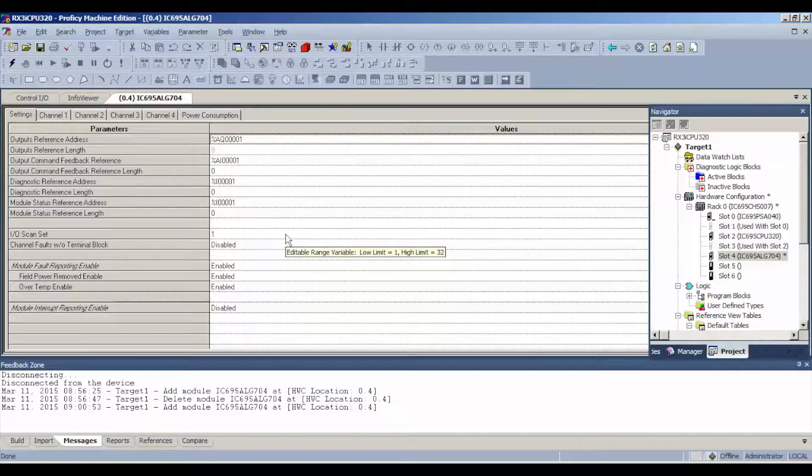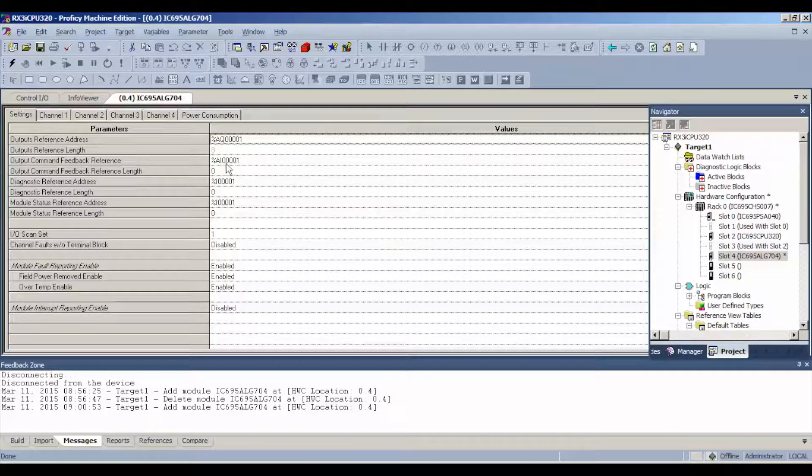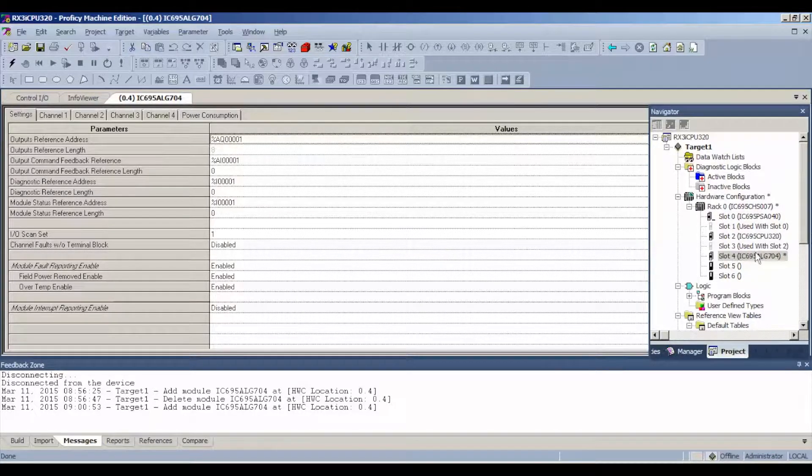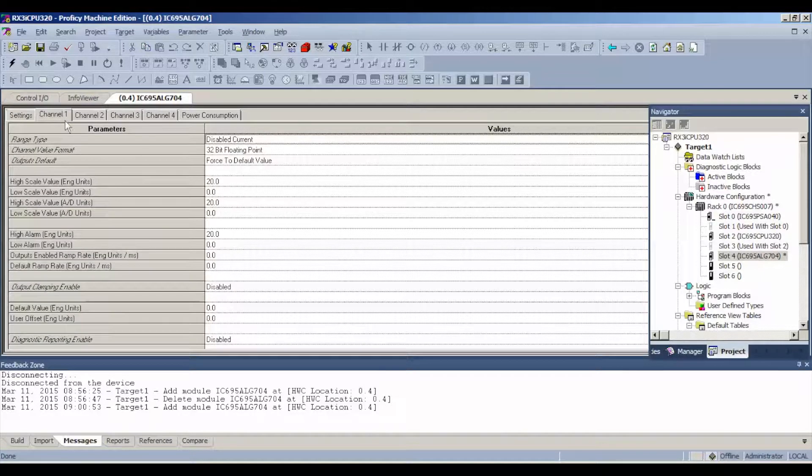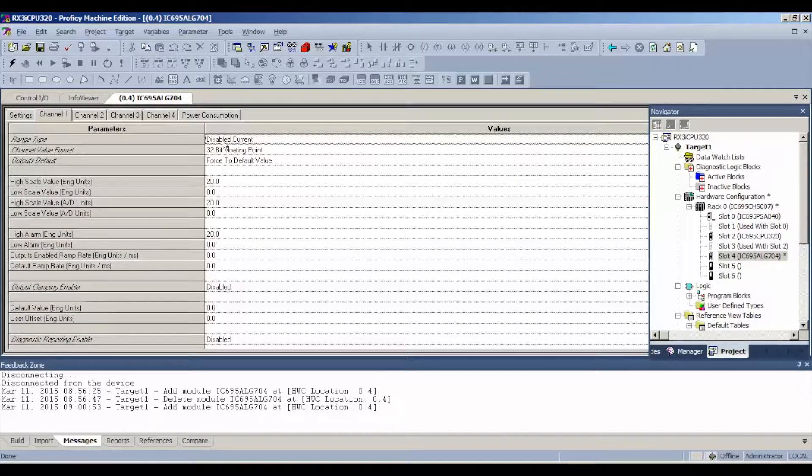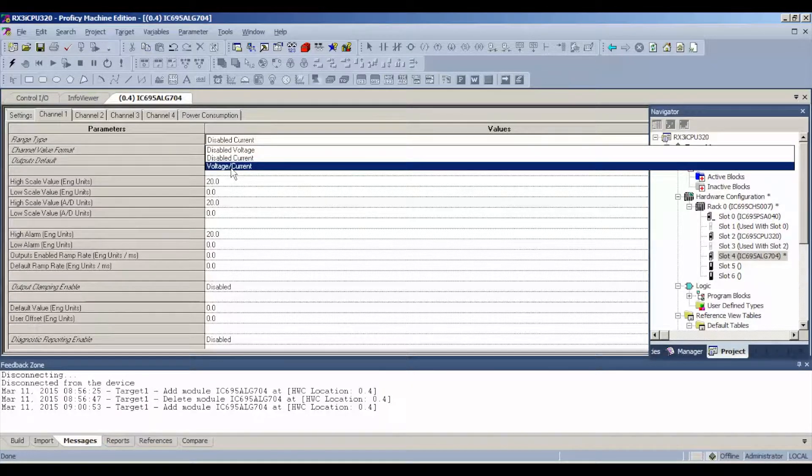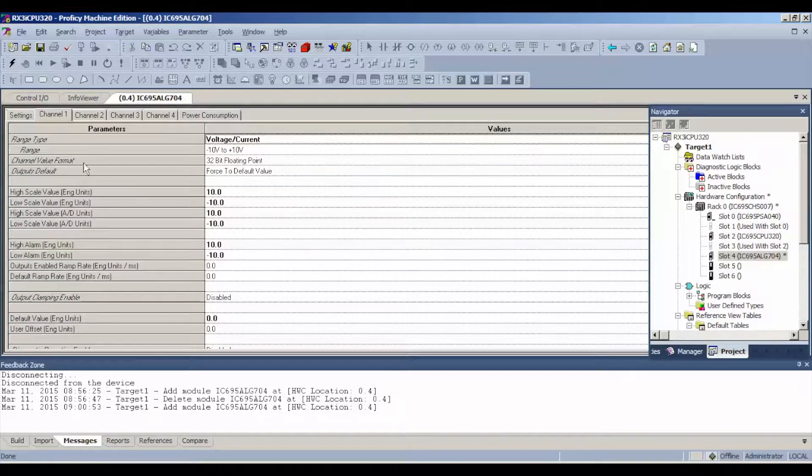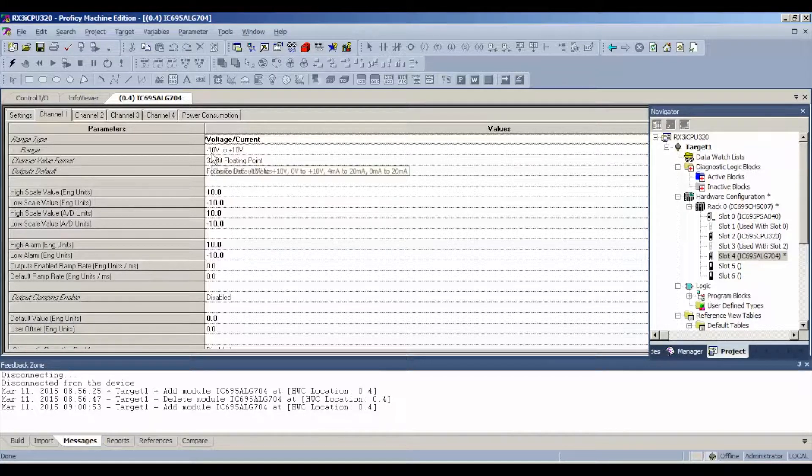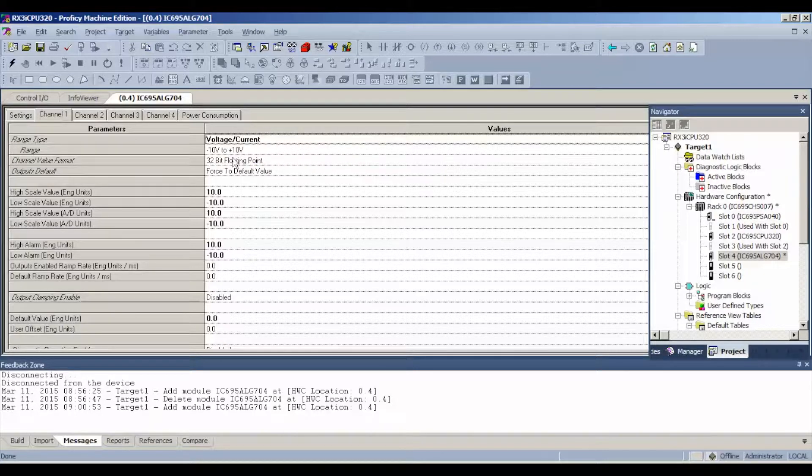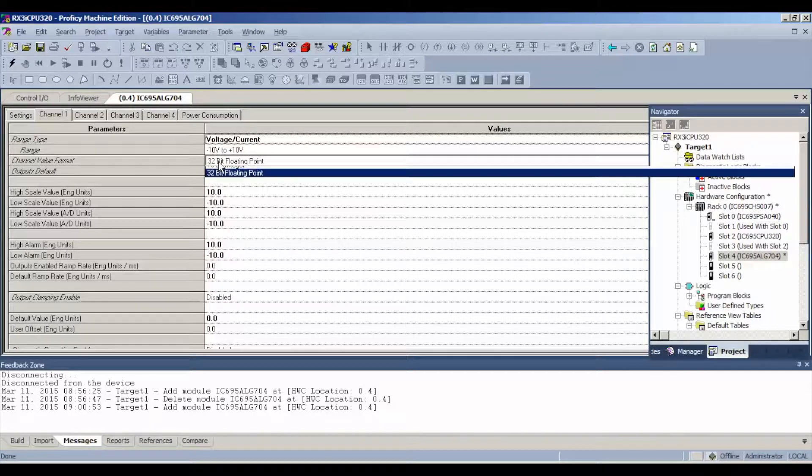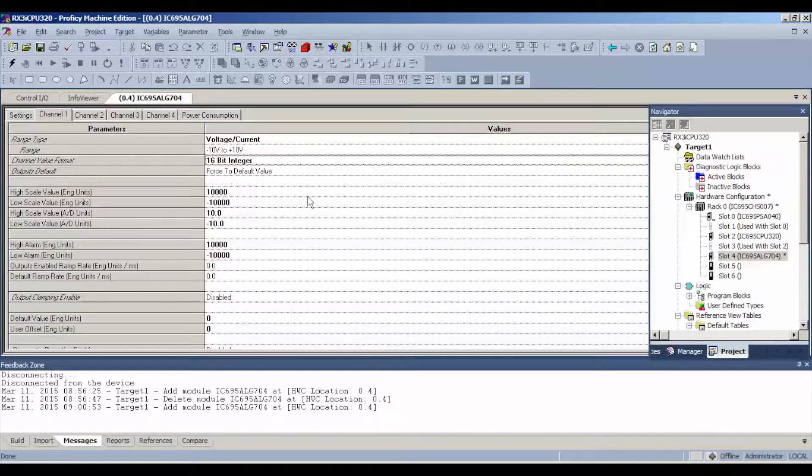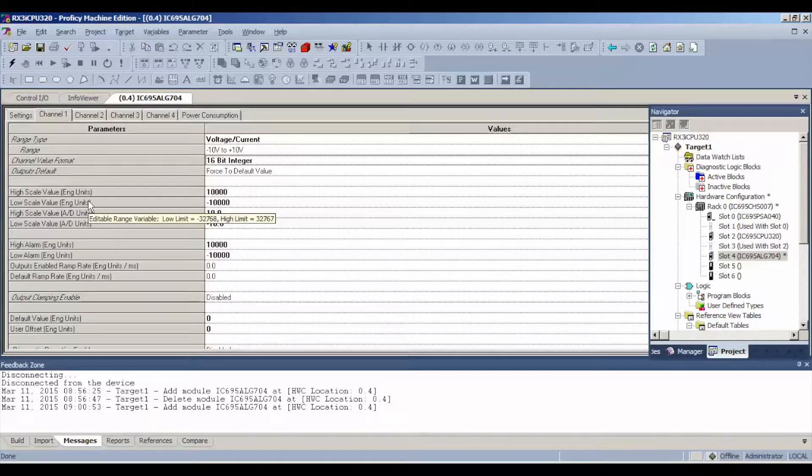The other settings we have to be concerned with is our channels. We'll go to channel one and we're going to go from our disabled circuit to a range of voltage or current. The range that it automatically goes to, the default range is negative 10 volts DC to positive 10 volts DC. That's fine. We'll start there. Our channel value format, we're going to use 16-bit integer and you'll notice that our maximum scale values are 10,000 or negative 10,000 if we want negative voltage.